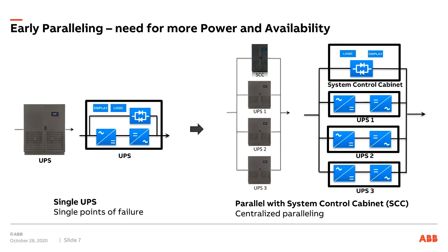The way paralleling was first done in the business was using a special version of the UPS and then a system control cabinet to control the operation of the parallel system. So the single line, the one line, and the illustration on the right show now we have 3 UPSs in parallel and 1 system control cabinet. And the UPSs are not really true UPSs. They're just rectifiers and inverters, and that's the way it used to be when we started paralleling UPSs. There's still some control in the UPS, obviously, to control the operation of the rectifier and the inverter. But the system control, like the load sharing and the synchronization, is all handled by the system control cabinet.